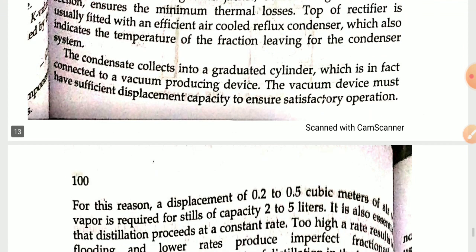The condensate collects into a graduated cylinder which is in effect connected to vacuum-producing devices. The vacuum device must have sufficient displacement capacity to ensure satisfactory operations.